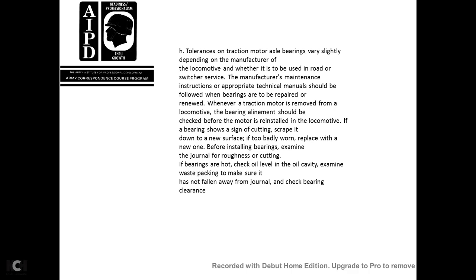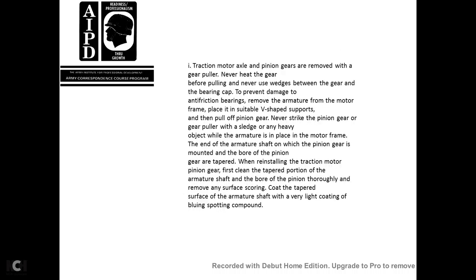Before installing bearings, examine the journal for roughness and cutting. If the bearings are hot, check the oil level in the oil cavity, examine the waste packing to make sure it has not fallen away from the journal, and check the bearing clearance. The traction motor axle pinion gears are removed with the gear puller. Never heat the gear before pulling. Never use wedges between the gear and the bearing cap.